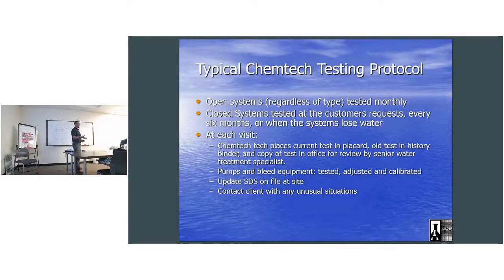The true way to figure out what type of glycol it is, you have to grab a sample and have a spectrophotometer do work on it. Do I have to send it in to you guys? We don't actually do it. We send it to a third-party lab because it's got to spin until it reduces out. It's like a $20,000 piece of equipment. But there are labs all over. There's a lab in Portland that'll do it. We're trying to track some of that down just to have some more local representation here.